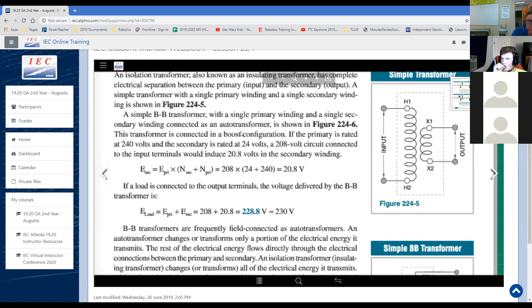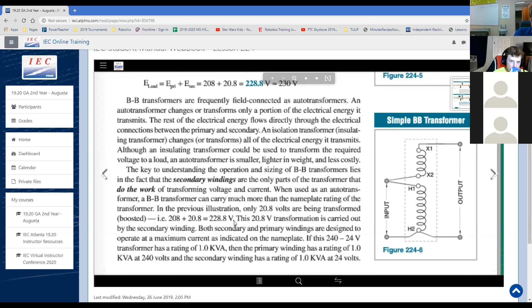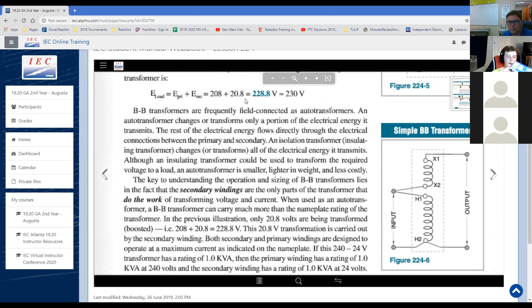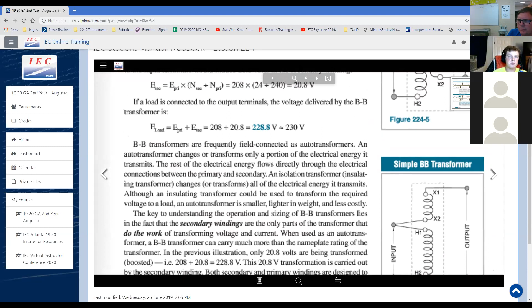And why would you do all this? What is the benefit of, why would you just not get a bigger transformer, which is what Cole would do. He'd get a bigger transformer, right? So instead of getting a bigger transformer, in the case of this thing, we can actually add a little buck boost, or boost transformer, and get 20.8 extra volts for our 208, and we can actually get our 230 on a run where, by the way, how do we get 208? Anybody know? How do we end up with 208?